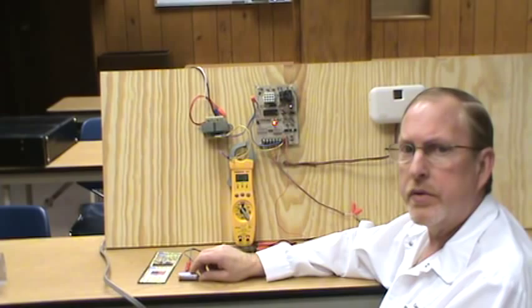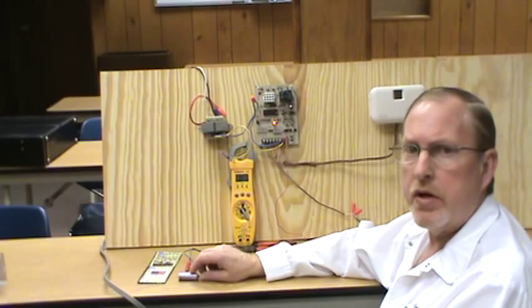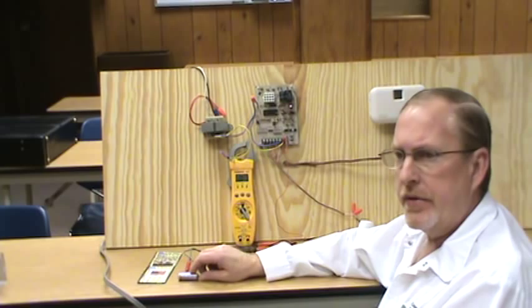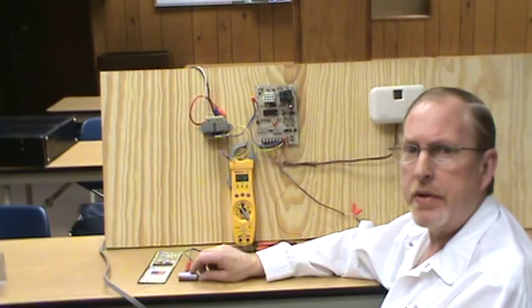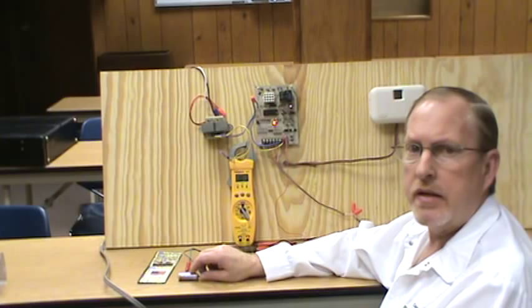Another method techs use is a manual reset type breaker with some leads on it where they jump out where the blown fuse was and start jumping out circuits until it pops the breaker. This is an alright method, although it can be time consuming, especially if you're outside trying to locate the short and it pops the breaker. You've got to constantly go back and forth to reset it.